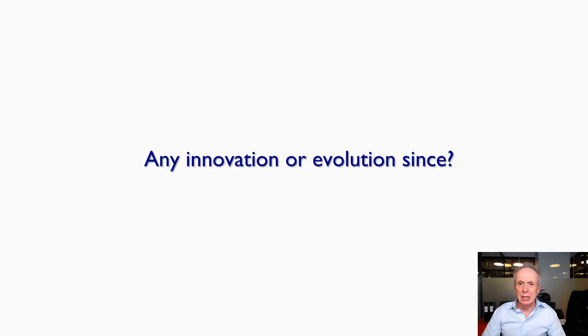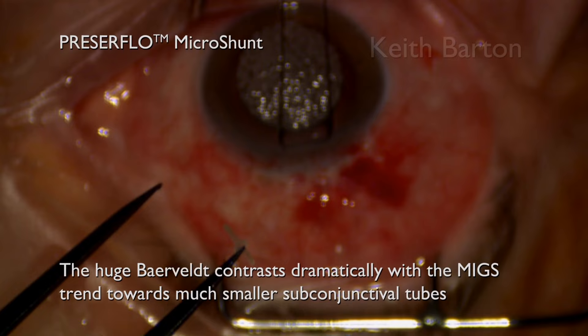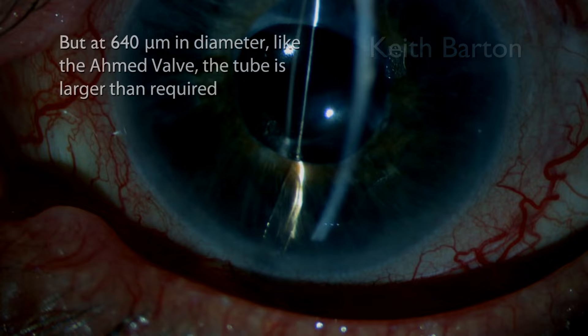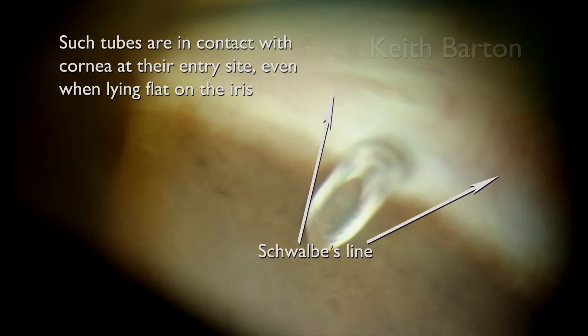What about new innovation? The Baerveldt implant is the most effective IOP-lowering implant available, but the plate is very large. The huge Baerveldt contrasts dramatically with the MIGS trend to much smaller tubes, such as the Xen and the Preserflo. The Baerveldt plate is large for good reason, as this is responsible for the long-term high efficacy level. But at 640 microns in diameter, like the Ahmed valve, the tube is larger than required. The 640-micron Baerveldt and Ahmed occupy the entire angle and are in contact with the cornea at their entry site, even when lying flat on the iris.